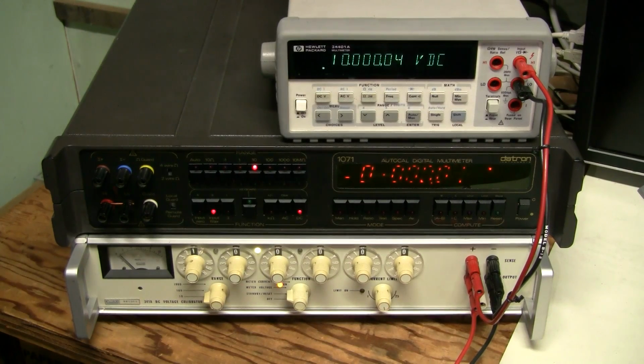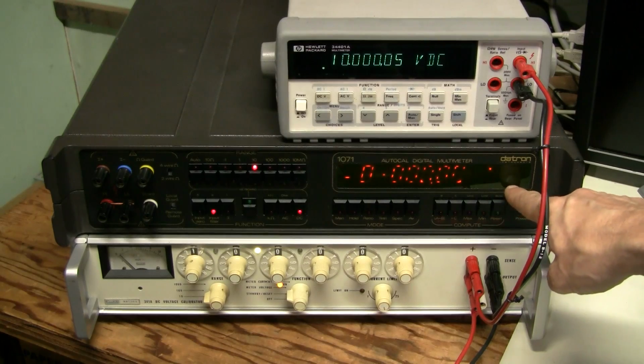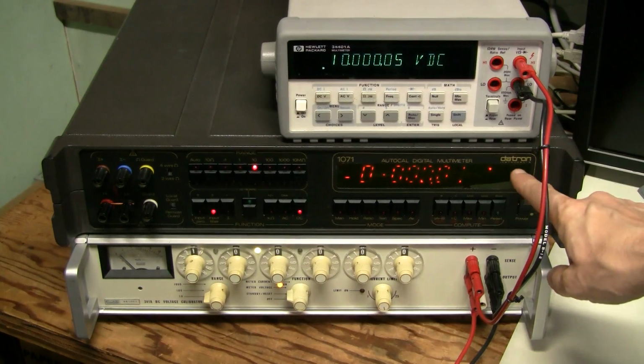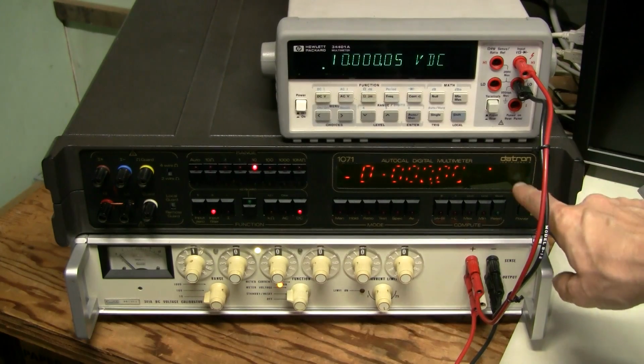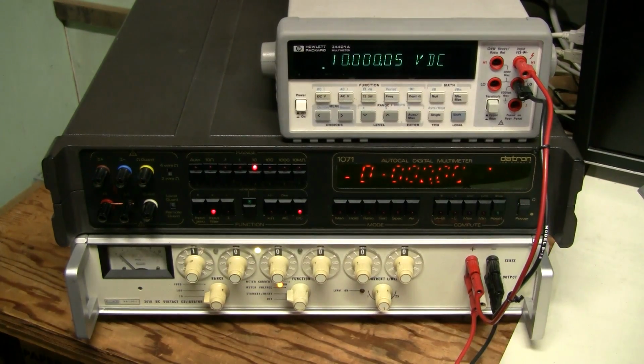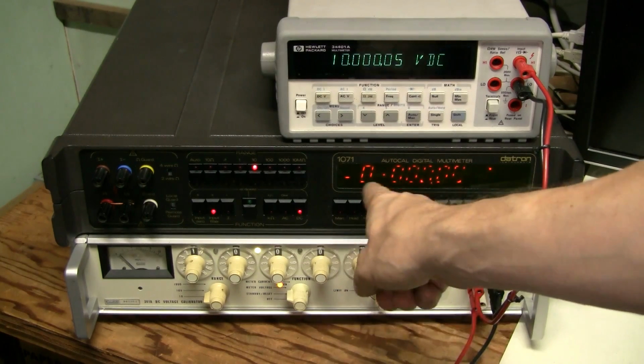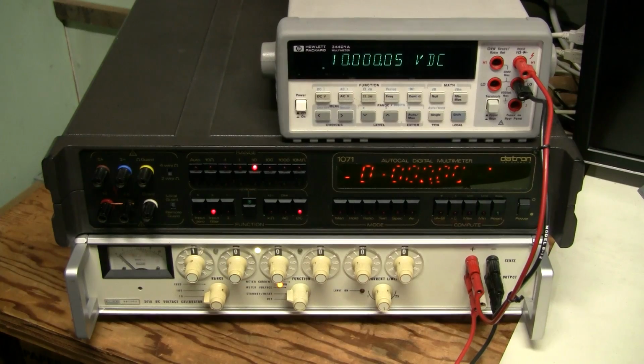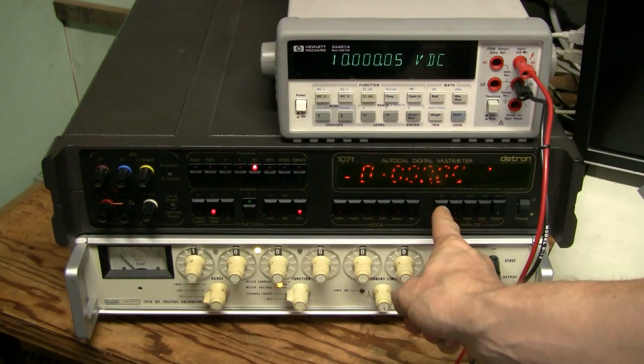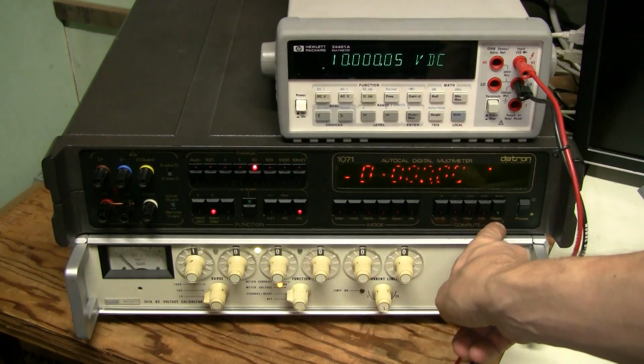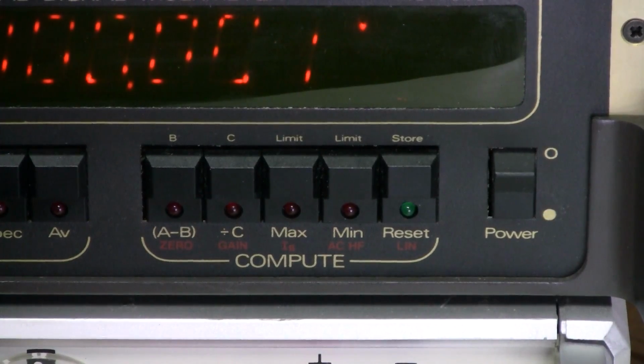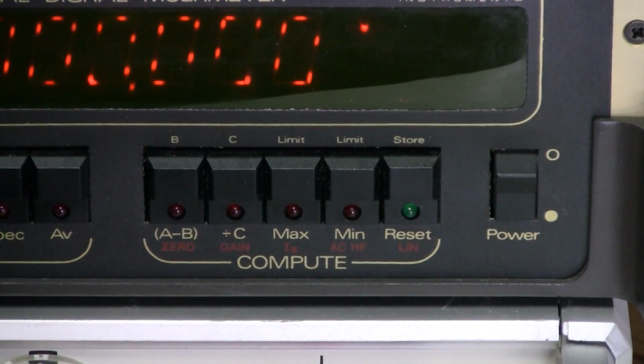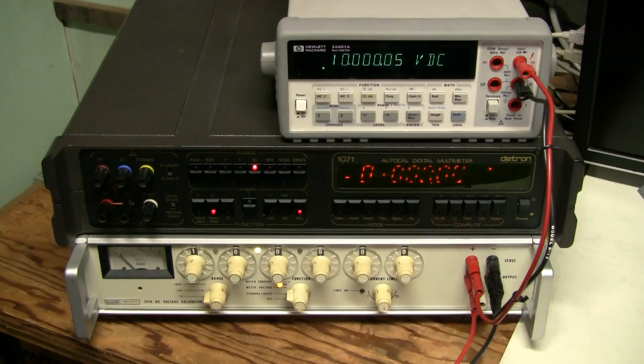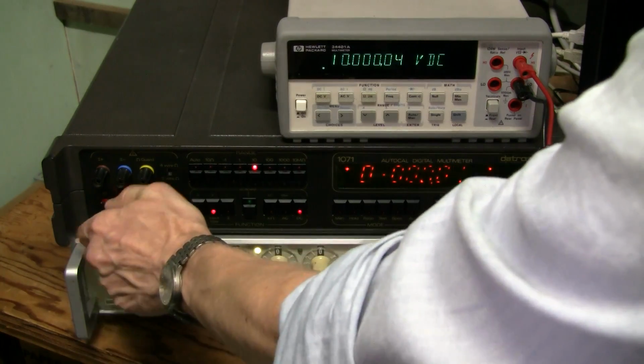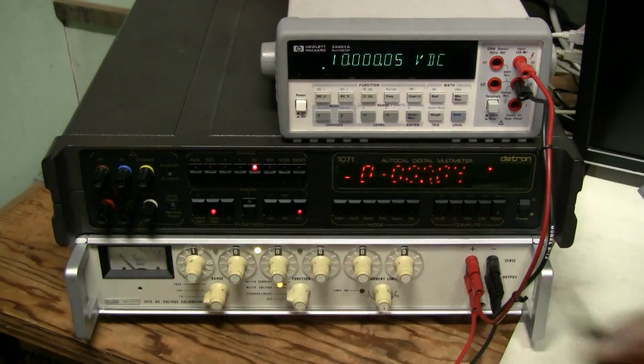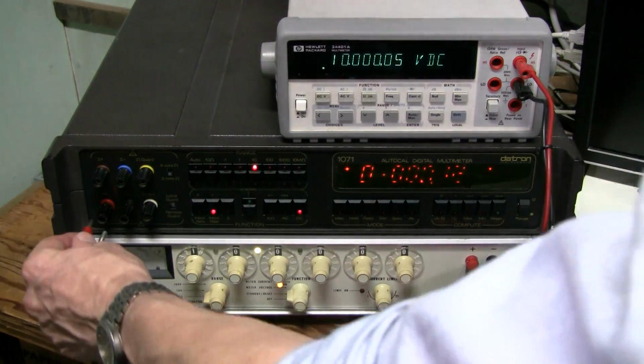So now we are in the calibration mode, and we are supposed to see cal indicator here, but this segment is not doing very well on the display. So we don't even see that cal. Anyway, it is very close to 0, so nothing to do here, but if we needed to set 0, this button should be used. There are red labels here which apply in calibration mode. So now let's remove the shorting link and connect the calibrator again.